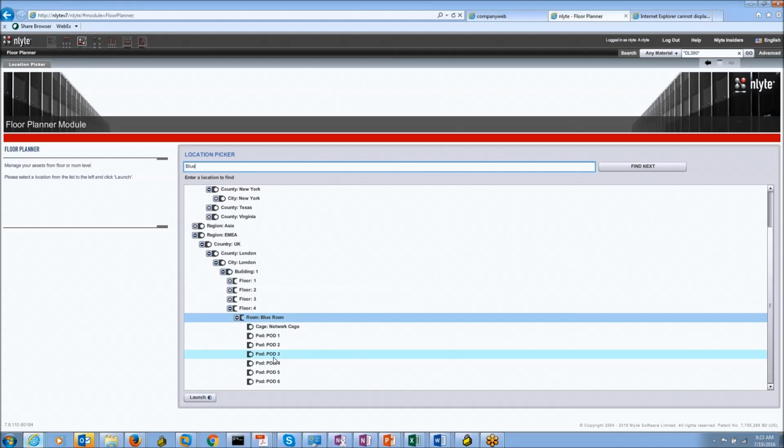It's important to think about how you might want to break this down and how you want to organize this, especially as you get down to the areas of a room piece, because each of these is like its own container that has properties of how many resources do I have in this container, how many am I using, and how many do I have left. So if I have only so many kW available to this room, then I can say, well, this is the percentage of what I'm using and what I have left.